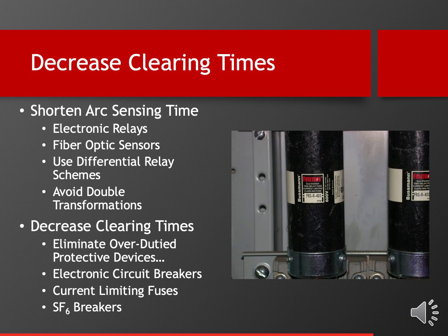And then finally, decrease clearing times. Well, eliminate overduty devices. That would help. If a device is not able to interrupt the current flow, it means that the next upstream device is going to do that, or you're going to melt something. And either way, it's a longer lasting arc than we want. So eliminating overduty devices is a good idea. Once again, those electronic breakers we talked about earlier are really a good idea. If you can use current limiting fuses, if you have a lot of fault current in your facility, a lot of short circuit current, limiting fuses are a godsend. They do a great job at lowering incident energy. Most often when you have high fault current and a current limiting fuse, the incident energy is 1 calorie or less. And so they're really a good device. And for those of you who work on more high voltage systems, sulfur hexafluoride or SF6 breakers are often a good option. So let's go to the next slide.